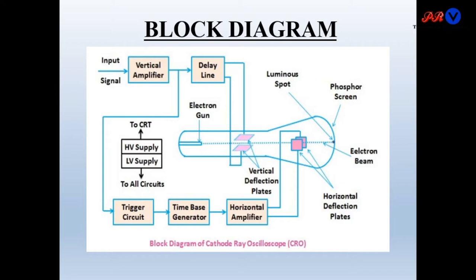This is the block diagram of the CRO. The input signal which we want to visualize is given to the vertical amplifier, which amplifies the input signal. A delay line produces some delay before it goes to the vertical deflection plates. From the vertical amplifier, another signal triggers the time base generator circuit, which produces a ramp voltage or sweep voltage that is amplified by the horizontal amplifier and goes to the horizontal deflection plates, moving the signal from left to right.